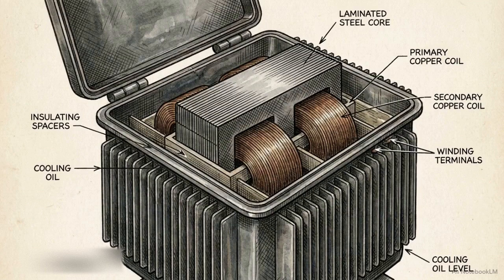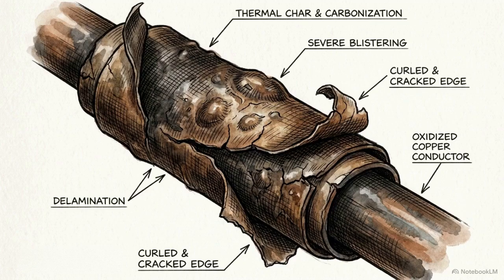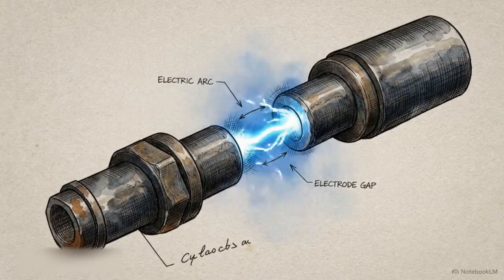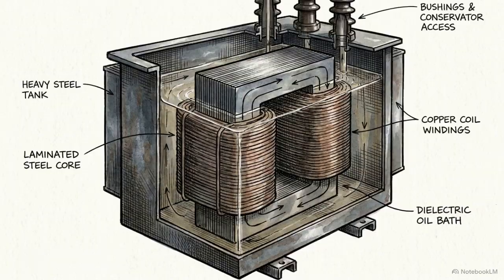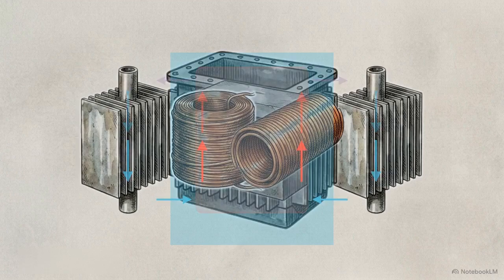To complete the build, the laminated core and copper windings are sealed inside a heavy steel tank. At the scale of a megawatt-level grid, even a 1% efficiency loss generates enough sustained heat to degrade the unit's internal insulation over time. High voltages also create the risk of corona discharge, a blue electrical arc that can leap across the gaps between internal components. To manage both threats, the tank is flooded with highly refined transformer oil. The oil acts as a convection coolant, rising from the core to external radiators before sinking back down.